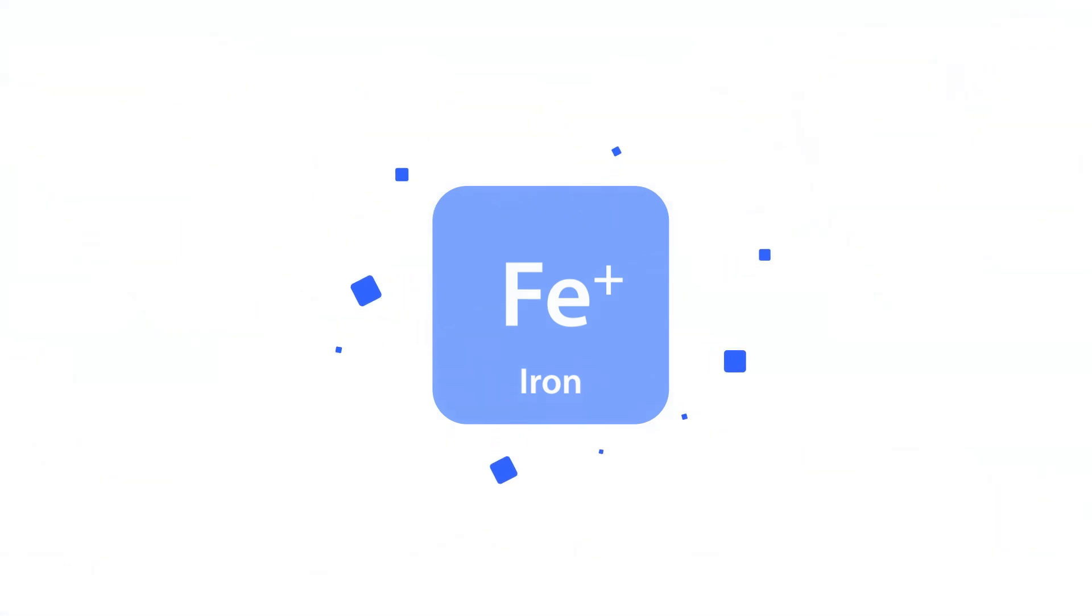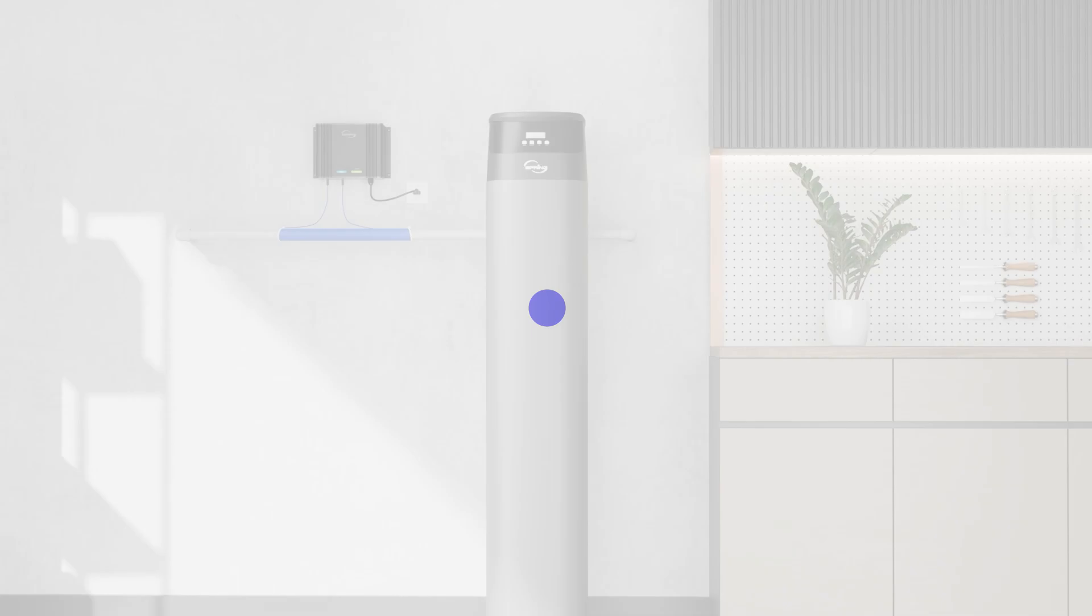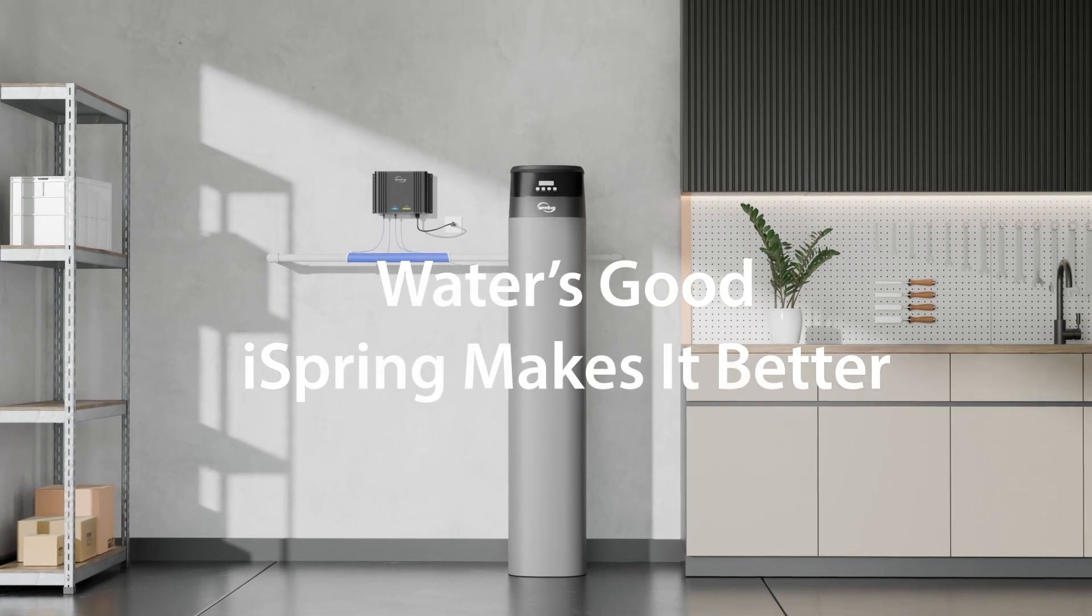High iron content in your water will also reduce the effectiveness of the EDV2. For source water with iron levels over 0.3 ppm, using an iron removal filter before the EDV2 is recommended.